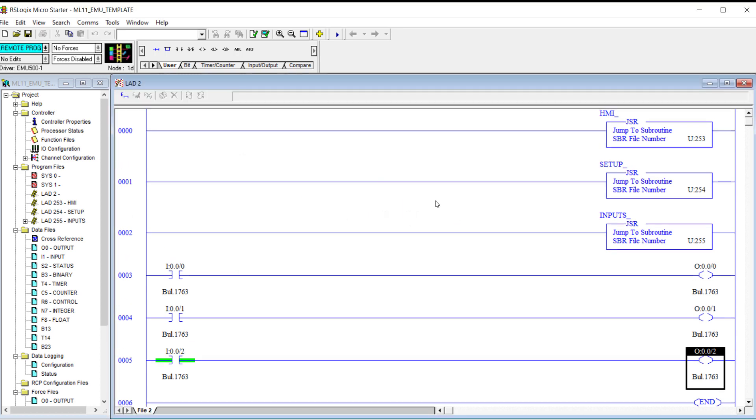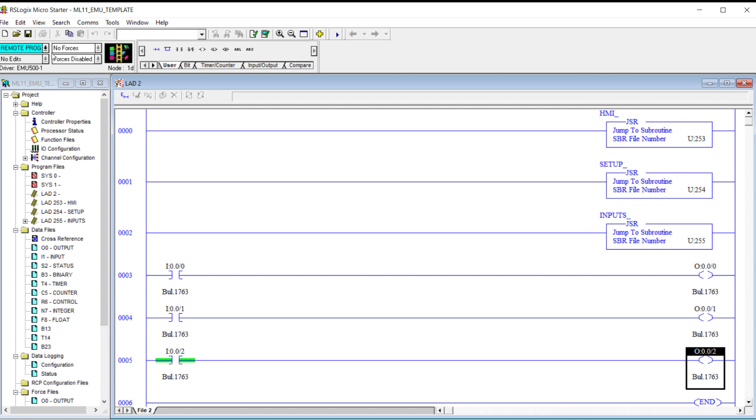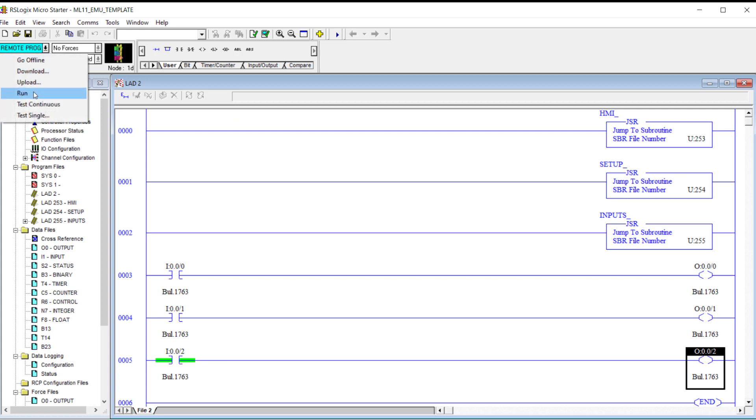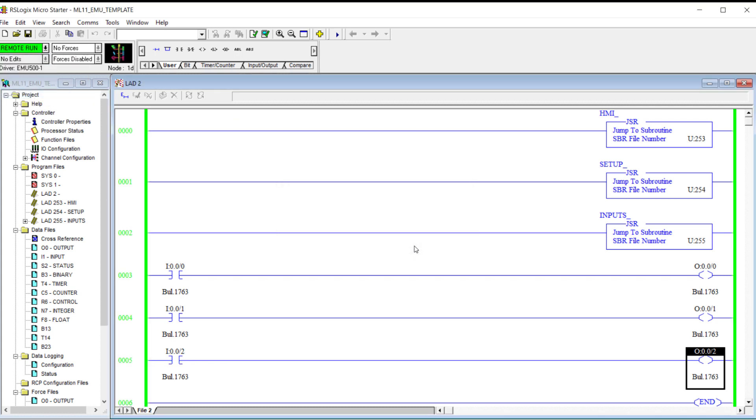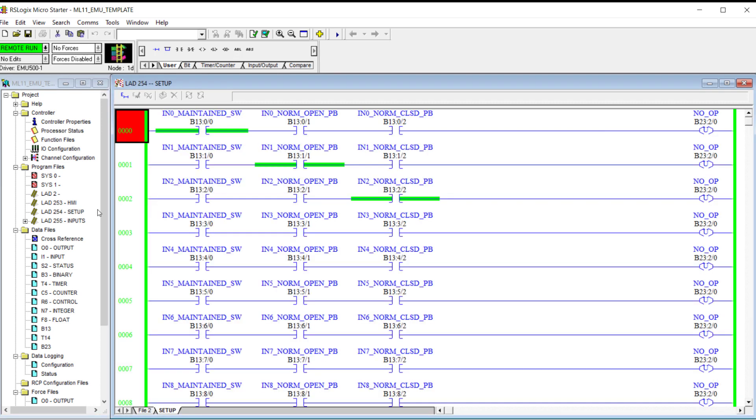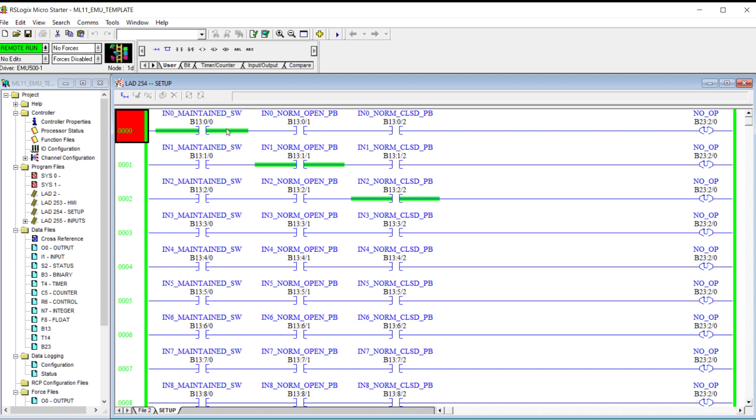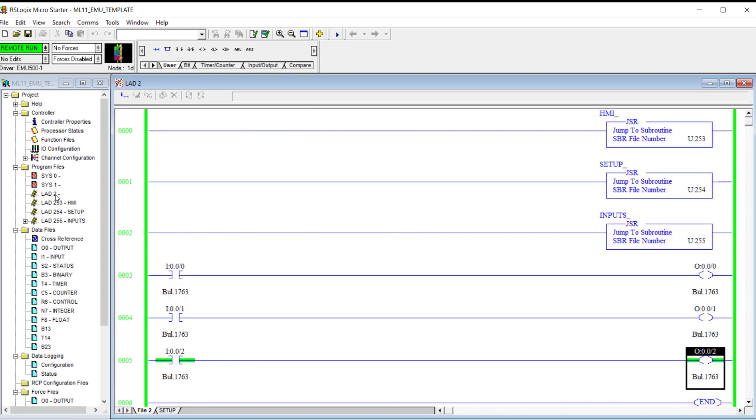So now I have three rungs. I'm going to verify and download. And the emulator always comes up in the remote program mode. So I'm going to select run. Now notice that input two is already on. That's because I set it up as a normally closed push button. Input one as a normally open push button. And input zero as a maintained switch. So keep that in mind. We could have gone and labeled them. And maybe that would have made it easier for you to look at.